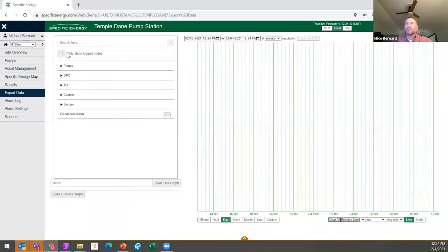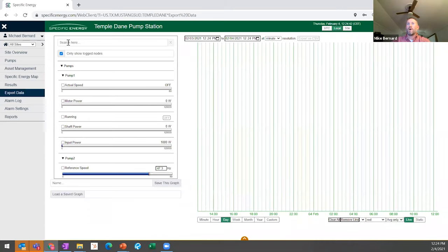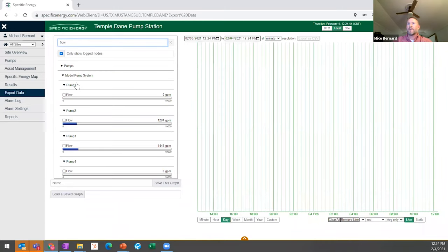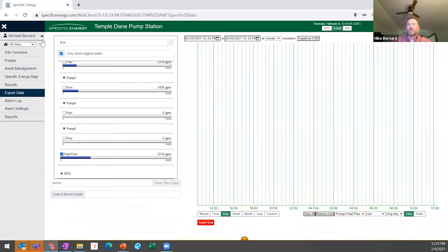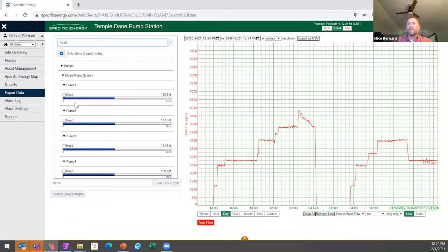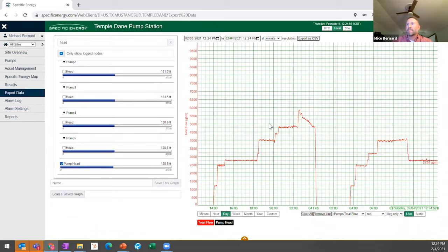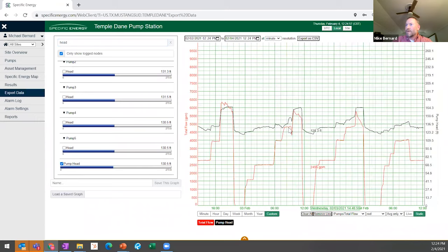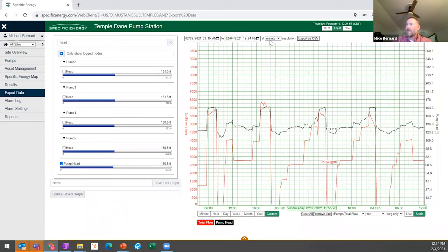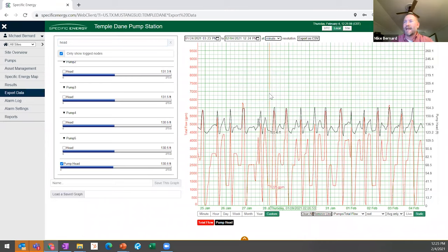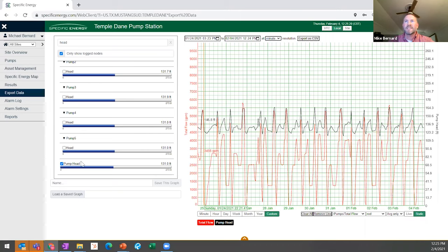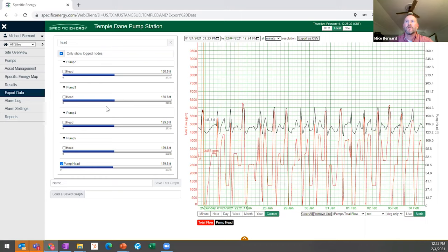Now, for the engineers on the call, I am one. One of my favorite things to do, every piece of data that we're logging can be exported from the system. So one of my favorite things to do is to come in here and pull the flow and pump head. I can grab a week, a month, a year's worth of data, whatever I want, export it at whatever resolution I want. And in essence, what I'm going to do is confirm the system curve that was used in design. I'm going to show you that here in just a minute as part of the case study and show you how different system curves may be than what your Innovyze model or your spreadsheet says it should be. We actually recommend that our customers give access to the system to their engineers so that they can help with capital improvement planning, situational awareness. We just believe that more eyes is going to lead to better optimization of these pumps.